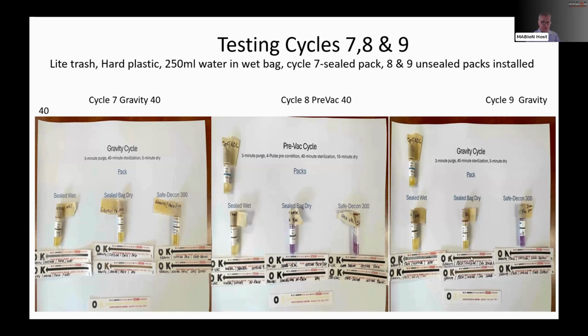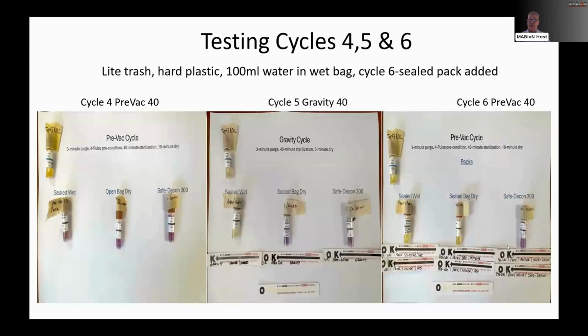Gravity again, this is where I have a problem with people running the gravity. If you're going to run gravity, you're just going to have to run it for a very, very, very long time. And you can see here, 3-minute purge, 40-minute sterilization. So these two, you can see that they were kind of light. This bag did burst on the wet bag. They did burst a lot. You can see the outside of it. I think the test strip probably just got wet. The inside was actually next to the BI. It's showing you that, yep, we got the steam, we got the heat. Didn't make it.